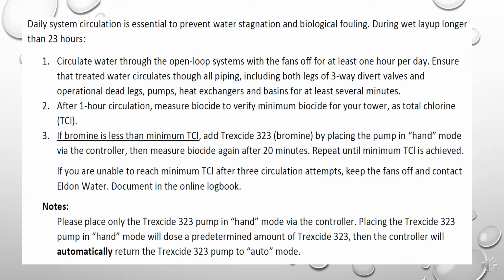Those operational dead legs are parts of your system that are able to receive circulation but might not receive circulation unless you indicate that the circulation needs to go there. So after the 1 hour circulation, that's when you measure your biocide to verify minimum biocide for your tower. If the biocide is less than the minimum total chlorine for your system, whether you're on that standard program, elevated program, or chlorine program, you want to add Trexide by placing the pump in hand mode via the controller. Then you want to measure it again.